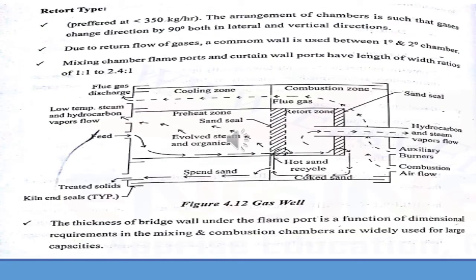The next type is the retort type, which has a capacity of less than 350 kg per hour. The arrangement of chambers is such that gases change direction by 90 degrees, both in lateral and vertical directions. A common wall is used between the primary and secondary chambers to enable return flow of gases. Mixing of gases takes place at a ratio of 1:1 to 2.4:1, and the thickness of the wall determines the mixing and compression capacity.